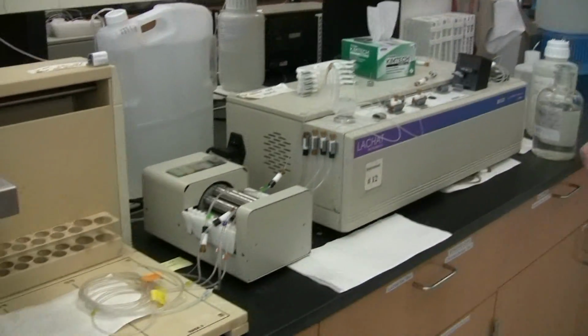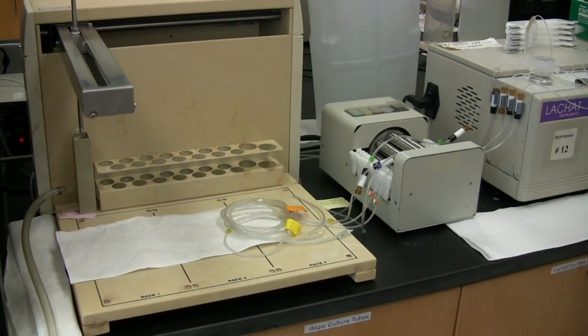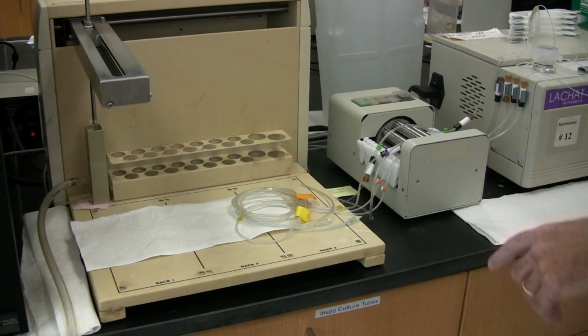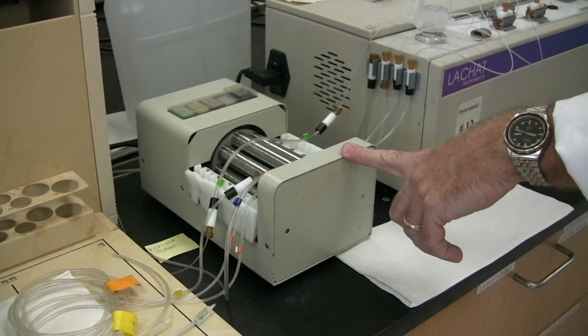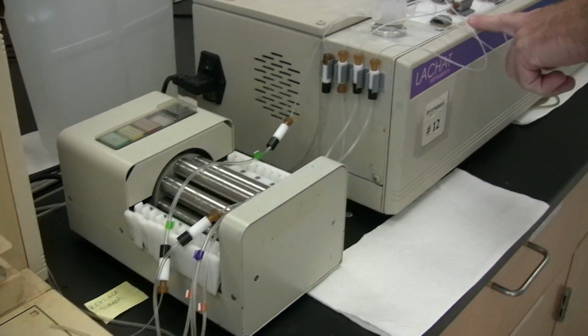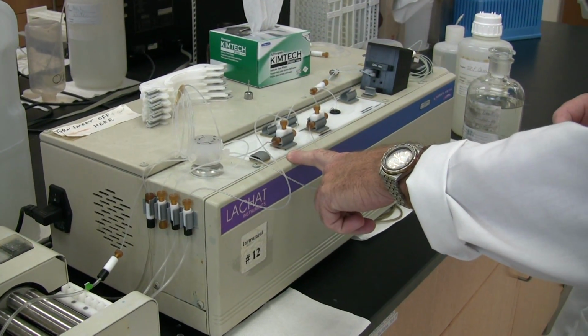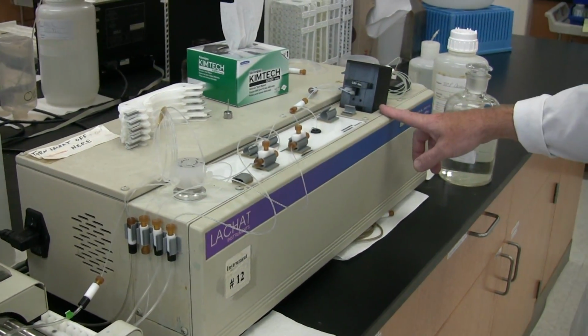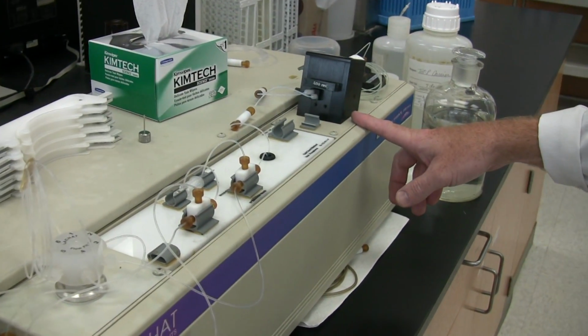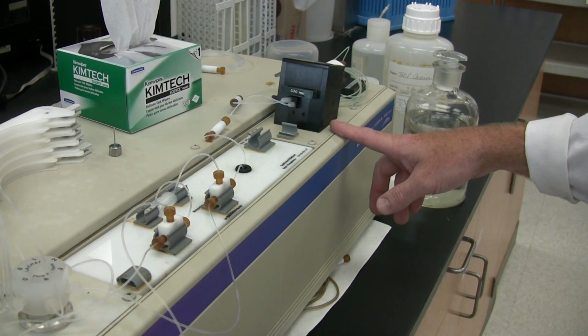This is a Lachat 8000. It's run by a PC. We have three major components: an autosampler, which has a probe and goes in XYZ coordinates to sample; a peristaltic pump that brings the sample and reagents to a manifold that mixes the reagents; and a colorimeter at 880 nanometers that measures the amount of absorbance, which is proportional to how much phosphorus is in the sample.